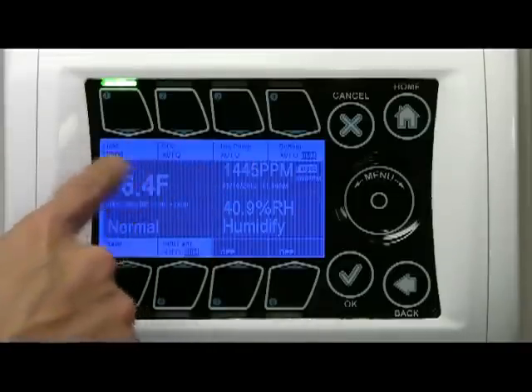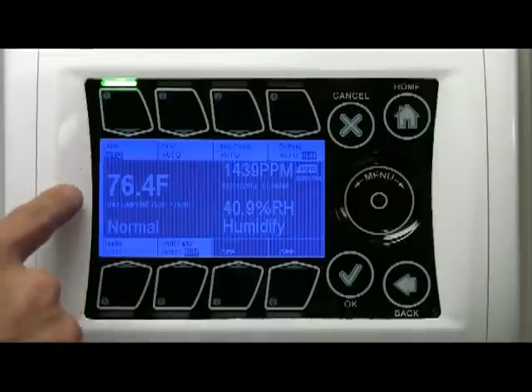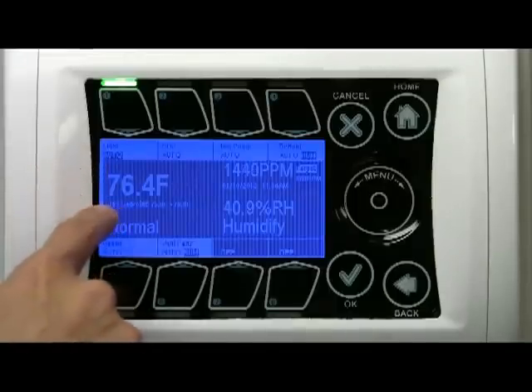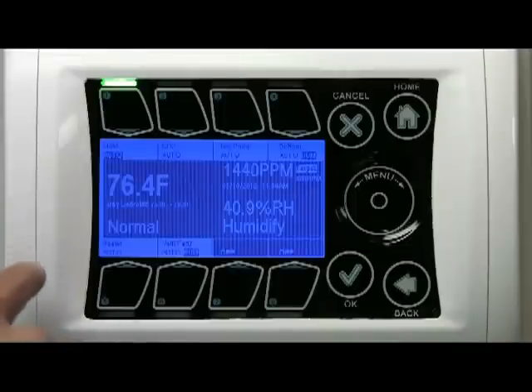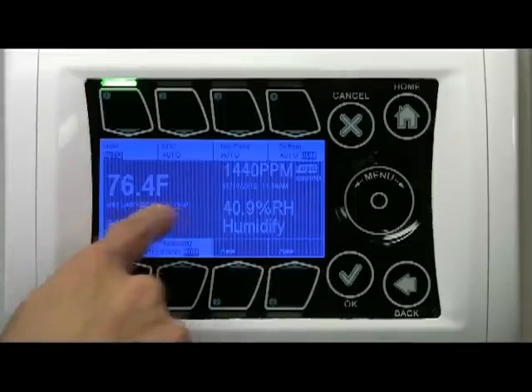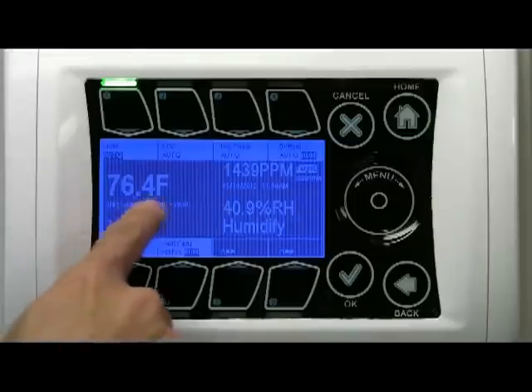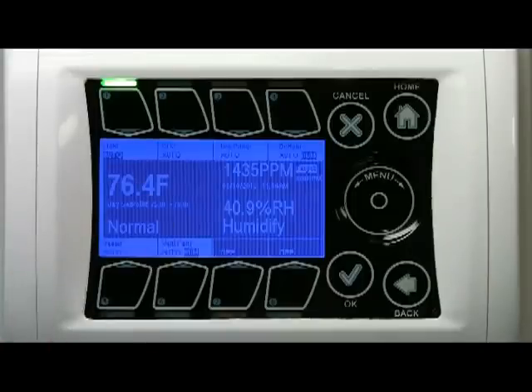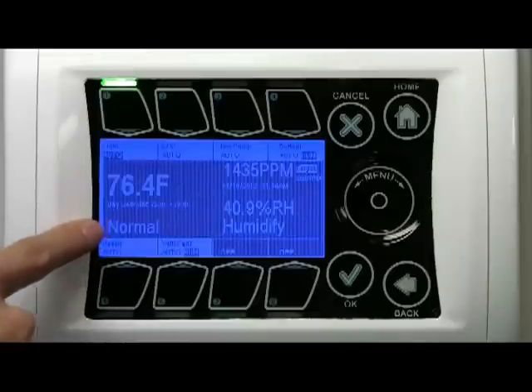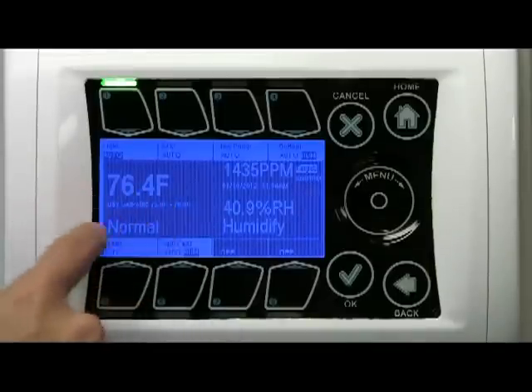Around the temperature reading you see something that's a day set point — that's the current set point of the unit: 75-78. That is the temperature target. Below 75 the unit will go to heating; above 78 the unit will go into its cooling mode. Right now it's in between, so it's in the normal stage.